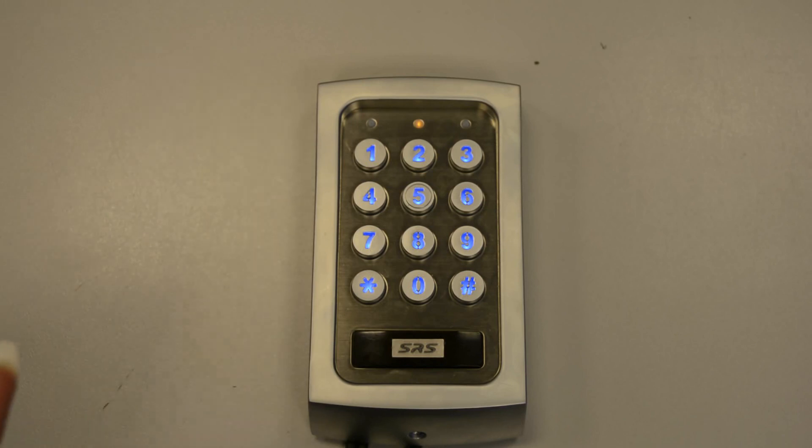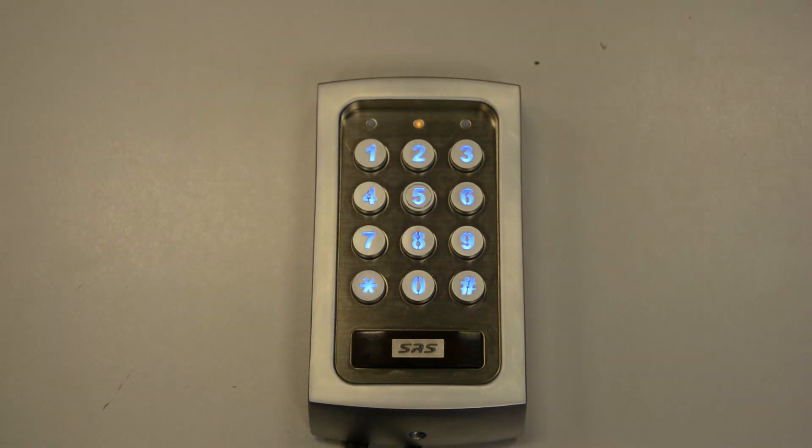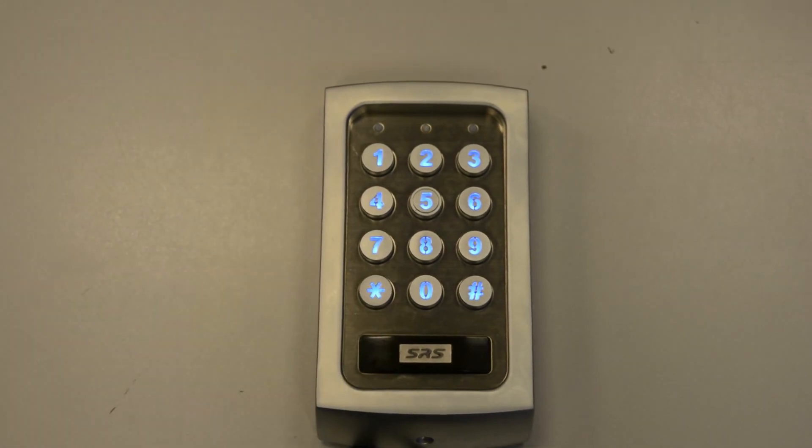So say for example I want to change it to 3 seconds, I'll enter the location number 51 — this is for output 1 — and then I'll enter 3, which is the number of seconds I would like relay 1 to change to. I'll then press hash to validate it; you will hear 2 beeps and then ** to exit programming mode.